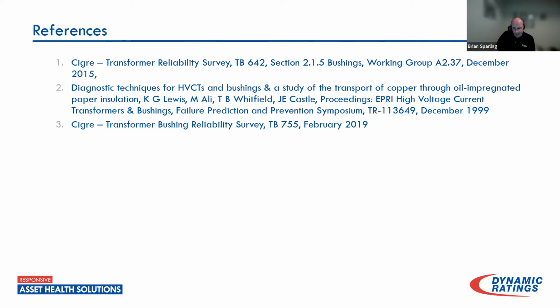And you saw in some of the charts I was showing that sometimes the trending is slow evolving. Sometimes the trend is a function of another parameter, like top oil temperature of the transformer in the case of bushings. And in the case of RIP bushings, trending over time when it takes off like a rocket is the indicator. Don't hang about, don't wait to see if it's going to go up another 10% or 5% in the next 5 minutes. Take action now. It's telling you that bushing was in distress. So it's all about trending.